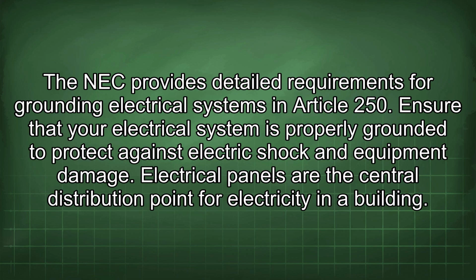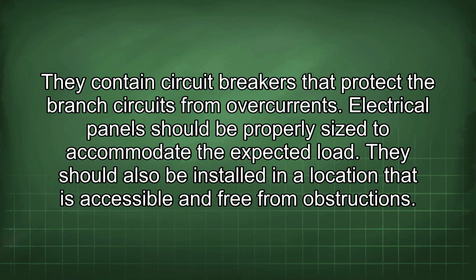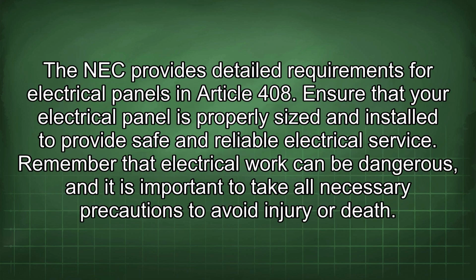Electrical panels are the central distribution point for electricity in a building. They contain circuit breakers that protect the branch circuits from overcurrents. Electrical panels should be properly sized to accommodate the expected load. They should also be installed in a location that is accessible and free from obstructions. The NEC provides detailed requirements for electrical panels in Article 408. Ensure that your electrical panel is properly sized and installed to provide safe and reliable electrical service.